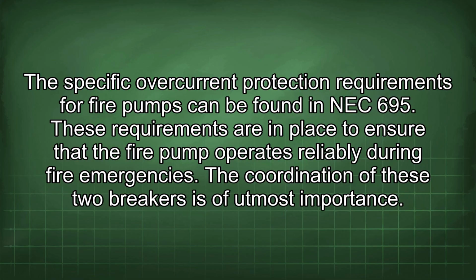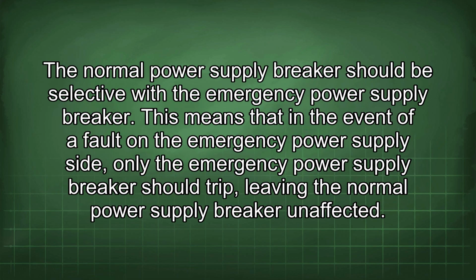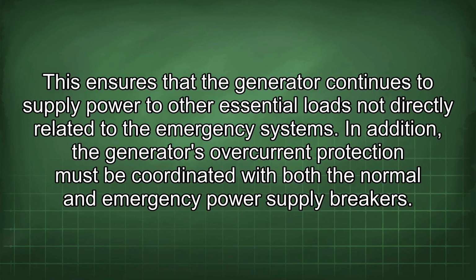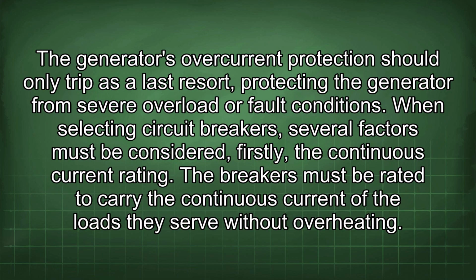The coordination of these two breakers is of utmost importance. The normal power supply breaker should be selective with the emergency power supply breaker. This means that in the event of a fault on the emergency power supply side, only the emergency power supply breaker should trip, leaving the normal power supply breaker unaffected. This ensures that the generator continues to supply power to other essential loads not directly related to the emergency systems. In addition, the generator's overcurrent protection must be coordinated with both the normal and emergency power supply breakers. The generator's overcurrent protection should only trip as a last resort, protecting the generator from severe overload or fault conditions.